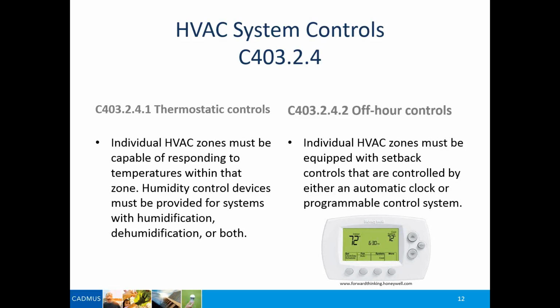Off-hour controls are important because if your building space is only going to be occupied from 8 in the morning until 6 o'clock at night, for example, there's no reason to have your system running full blast from the time your business shuts down until the next morning. So it's best to set the system up to be able to operate it at a higher temperature, and you'll save energy that way. And you're probably already doing this right now. So setback controls are required on all systems. So this is kind of the key thing. You have to have a control. It's got to be a setback.